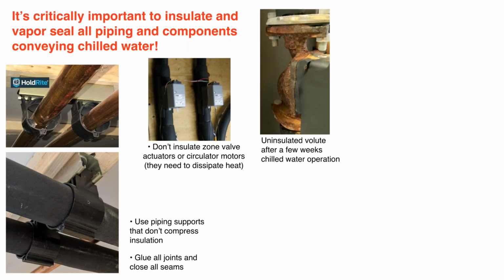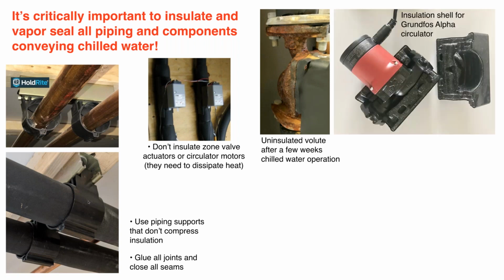Now, there's a corroded volute on a circulator, literally 6 weeks of operation from a brand new product to that in 6 weeks. I'm not sure what the coating was. That was not bare cast iron. It had some type of a paint or a coating on it, but it shows you how serious this issue of insulating chill water piping is.